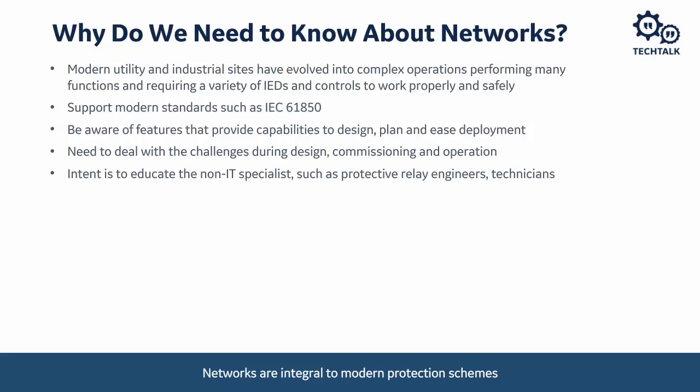IEDs in our industry means intelligent electronic devices, which cover a wide base of microprocessor-based devices such as relays, sensors, meters, and data acquisition units. Notably, with the advent of IEC 61850 standards, this has encouraged relay vendors into speeding up the development of Ethernet as a preferred method of communication. The benefits of Ethernet networking are tenfold, and flexibility and easy deployment are only two of them.